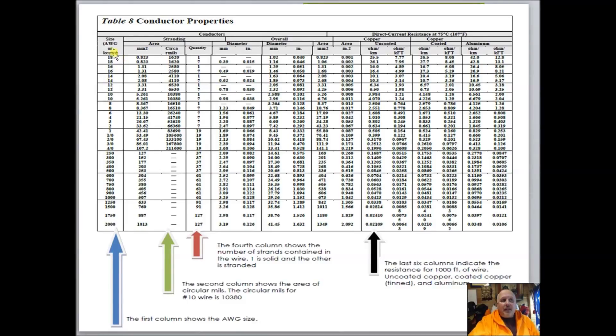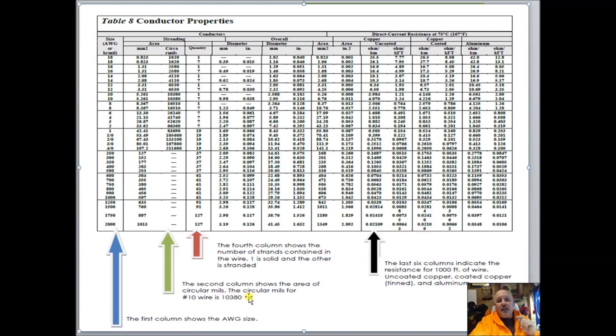That's Table 8. The first column gives you the AWG — American Wire Gauge — starting with smaller wires at the top going down to larger wires at the bottom. The next column gives you the circular mills of that wire, which we'll need for voltage drop calculations and for finding exact K. The next column is quantity — whether the wire is stranded or solid. The far column shows ohms per thousand feet for uncoated wire.